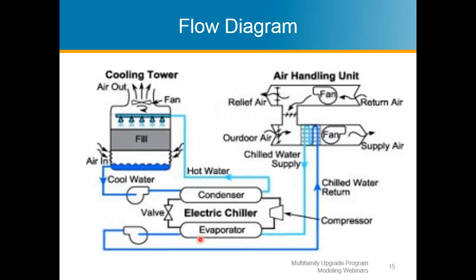So I'll show you that flow diagram again. Now that I've gone through it, it might make more sense. Again, the evaporator is the side going into your space, and the temperature of that water really depends on the specs of your chiller and where it's being installed. It runs through your coils. The warmer water then comes back and goes to the condenser side, and that hot water goes over to the cooling tower to remove the heat, basically taking that heat out to the outdoors, much like you see with a condensing unit at your house. It's the same deal. And then it goes back through and does the whole cycle again. So that, in a nutshell, is what the cooling side of a central plant is doing.